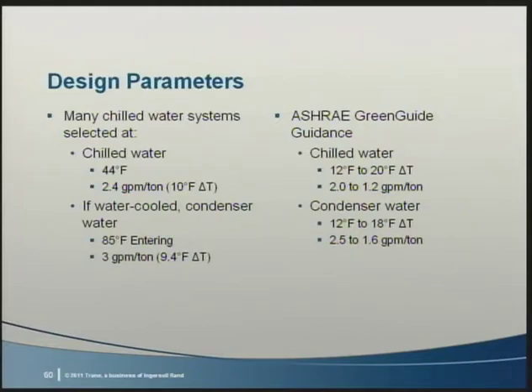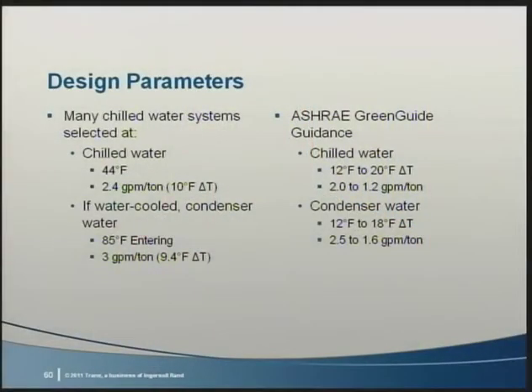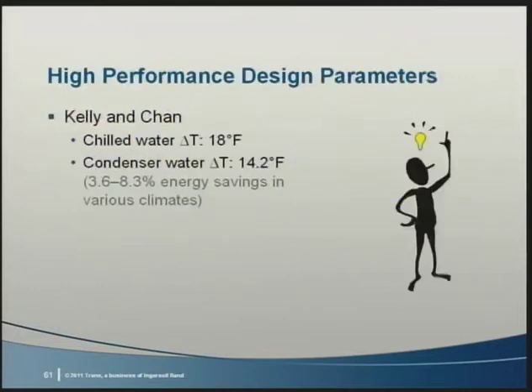Yet today, the ASHRAE Green Guide recommends expanding the chilled and condenser water temperature differences and reducing the respective flow rates. For example, on the chilled water side, the Green Guide suggests a 12 to 20 degree delta T and condenser water delta T of 12 to 18 degrees. Kelly and Chan, who were consulting engineers in Boston, performed a study and wrote a paper that recommends similar numbers. Now, what prompts their and the ASHRAE recommendations?